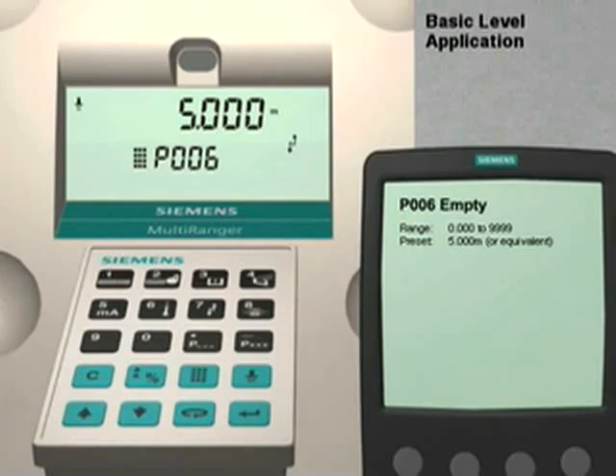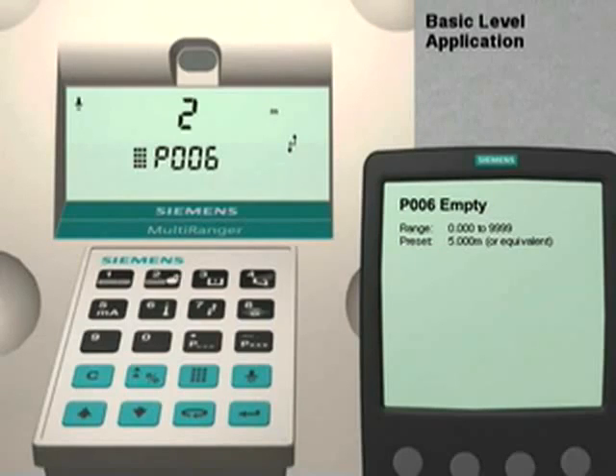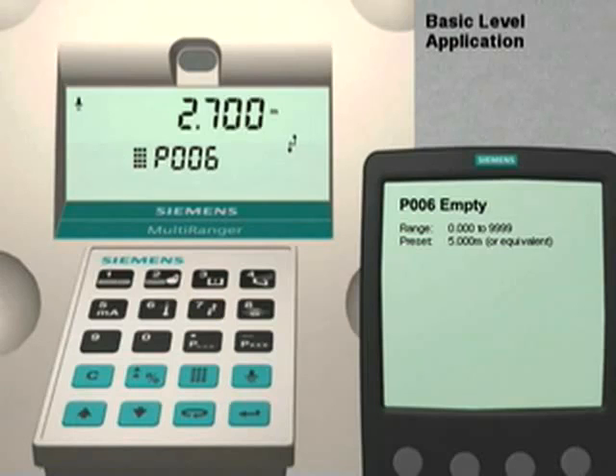Parameter 6 is the empty distance value. This distance is measured from the transducer face to the bottom of the vessel. For our application, this distance is 2.7 meters. To enter this value, press 2, decimal 7, and then the Enter key.